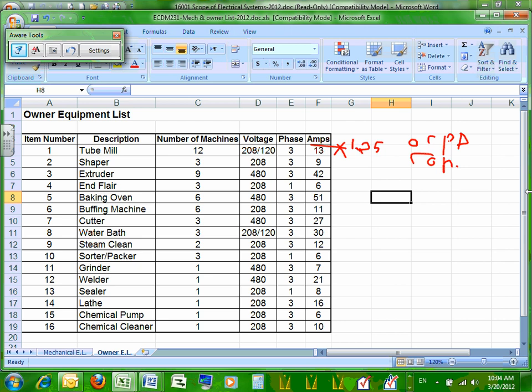A question came from Chris: would we treat them like motors? Because if you treat them like motors, you have to size the overcurrent protection device at 2.5, whereas I always multiplied by 1.25 and sized the overcurrent protection device. Well, you don't have to size by 2.5. You're allowed to size at 2.5 for a motor. If it's a piece of equipment, we could size it at 125%. Yeah. Well, there's an 80% demand factor, so there's the gate.